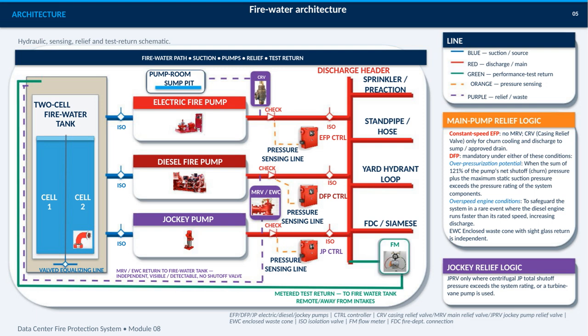From that header, protection is distributed to the sprinkler or pre-action system, standpipes and hose connections, the yard hydrant loop, and the fire department connection, or FDC. The green path is the metered performance test return, routed back to the tank and located remotely from the intakes. Relief and waste paths are shown in purple, including the diesel pump's main relief logic and the enclosed waste cone with a visible return. Finally, orange pressure sensing lines connect the pumps to their controls.